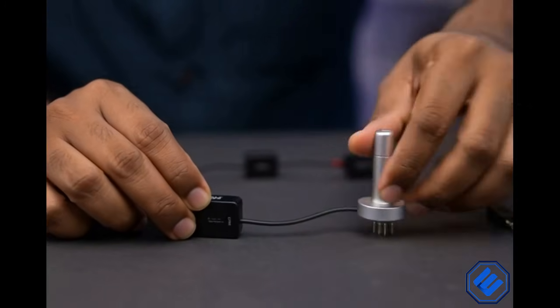Here's the good news though. Most sensor problems aren't random. They usually come down to a few common and completely avoidable mistakes in wiring and maintenance. Today, we're going to fix that. Here's the plan. First, the fundamentals of bulletproof wiring. Then step-by-step wiring for temperature sensors. After that, pressure sensors and the 4 to 20 milliamp loop. And a simple pro-level maintenance checklist. And finally, fast troubleshooting for common sensor headaches. By the end of this video, you'll be wiring and maintaining sensors with total confidence.